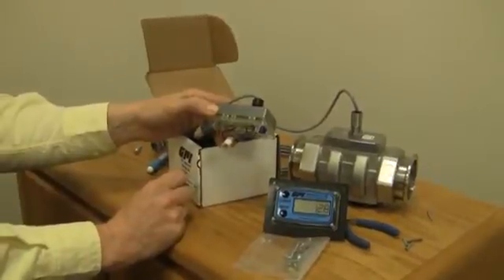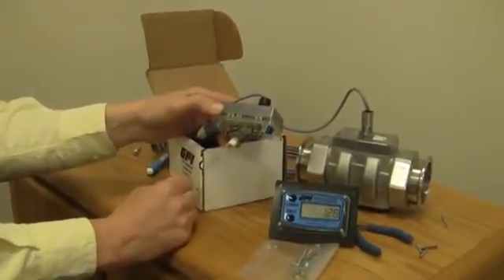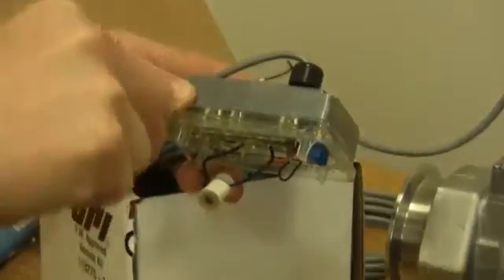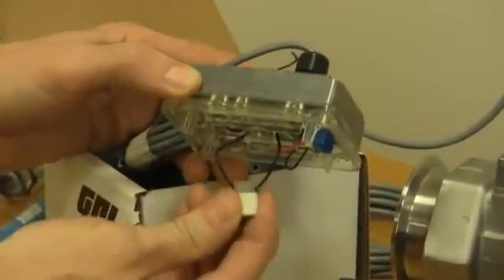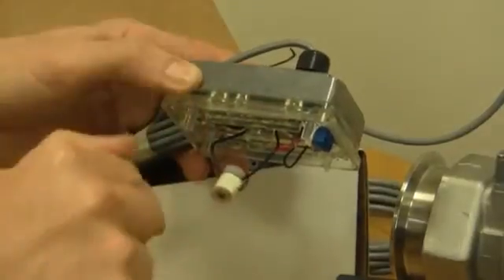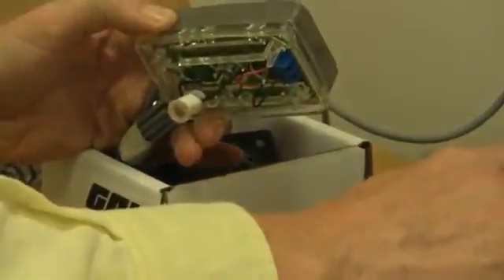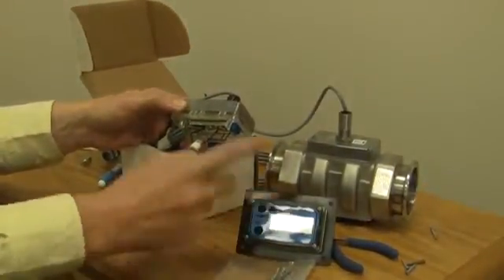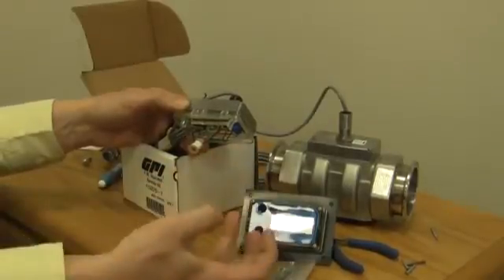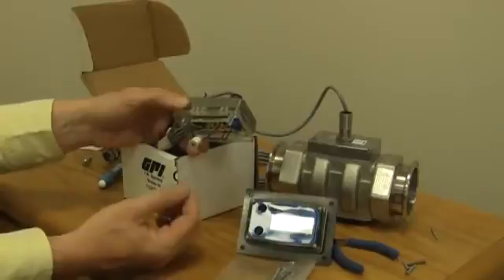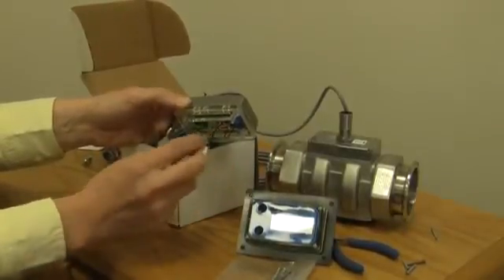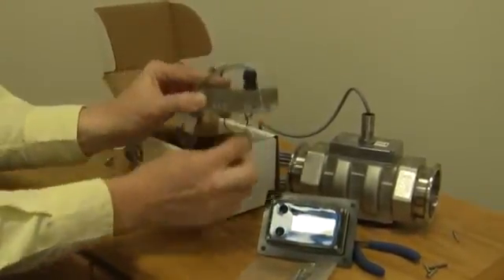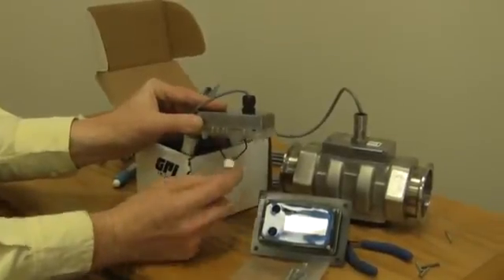Now also remember I said this is the one that you want to use for one of the PVC, the gray TM meters. The reason you need that is because the magnetic pickup has to go deep into a hole on the body itself, and this magnetic pickup is small enough to fit down into that hole while this one is just a little too large to get down in that hole. Now also your, excuse me, the display you took off of there, that magnetic pickup on one of the TMs had several little spongy pieces in there or some of them have a little hard plastic piece. You would actually take them off of that one, put them on here so it fits down onto that TM meter just like the old display did.